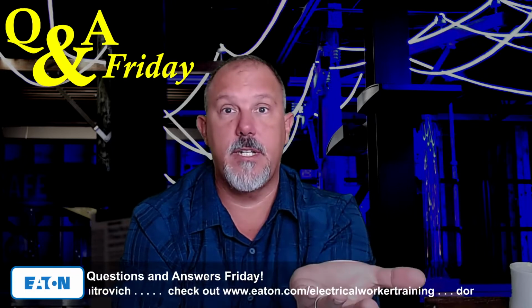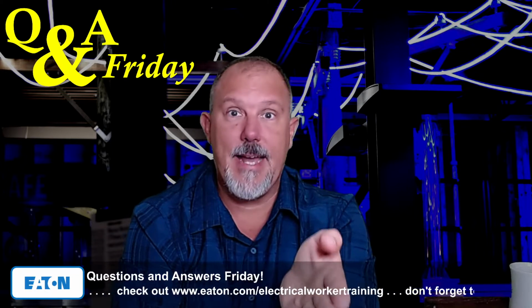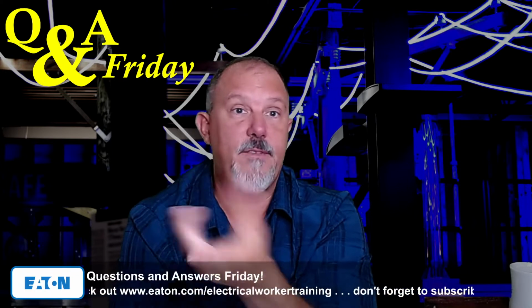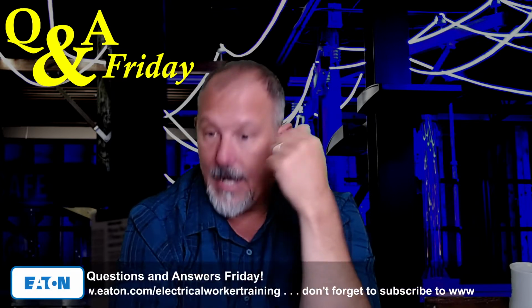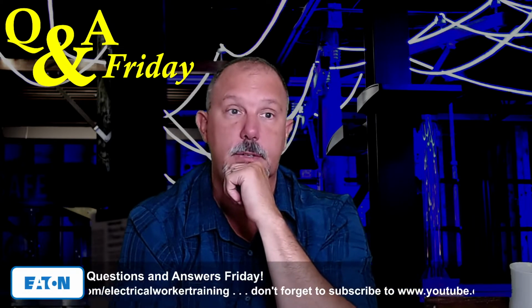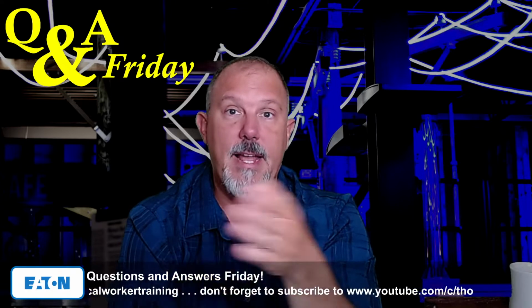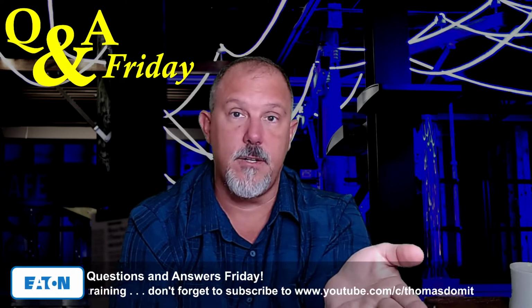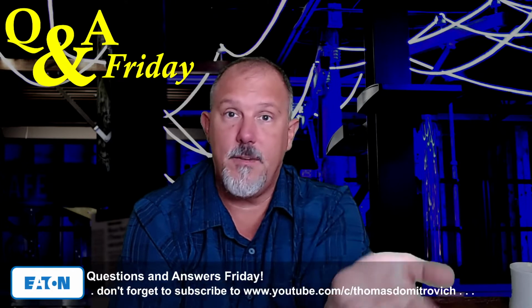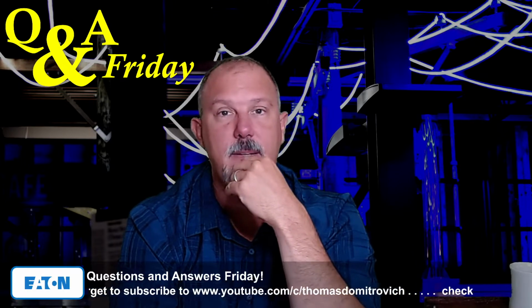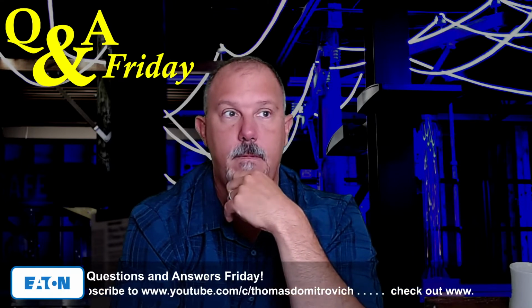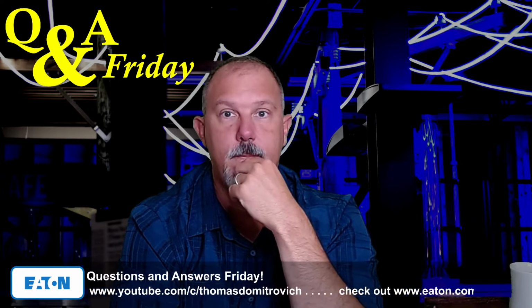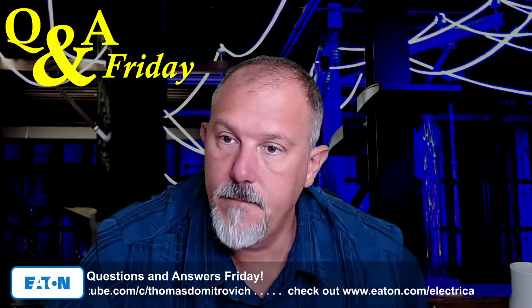I put a smaller conductor and I adjust it down, so the breaker physically, if I adjusted it all the way up to 1200 amps, I can carry 1200 amps worth of current, but I'm not. I'm carrying 80% of that on a conductor, and that's at 100%. So I really got to think about that one.